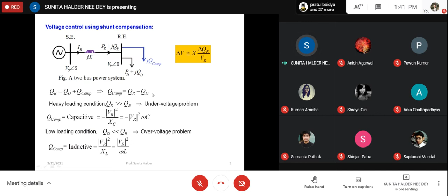Next, what may be the problem associated with shunt compensation? Obviously, if you connect a capacitor and there is a nearby inductor, that may create parallel resonance. Resonance means either very high current or very low current, so the power will not flow at the desired path. So resonance circuits should be avoided - there is a chance of parallel resonance that should be avoided.